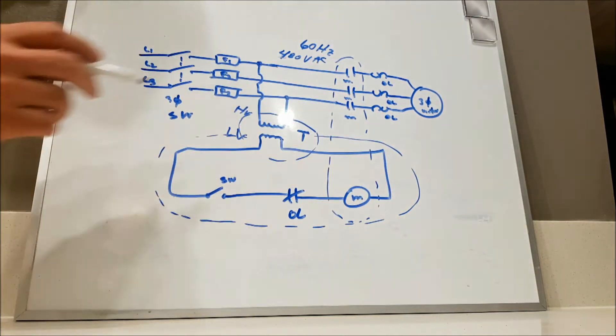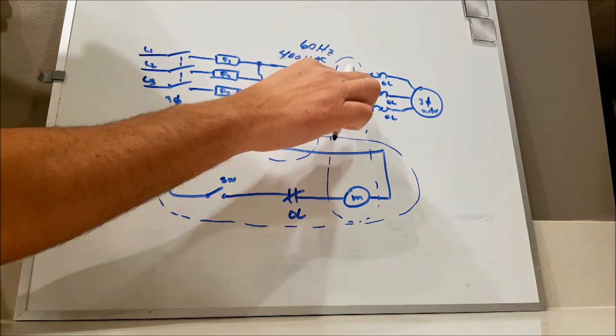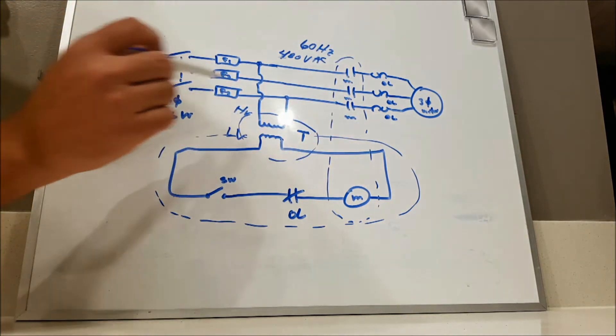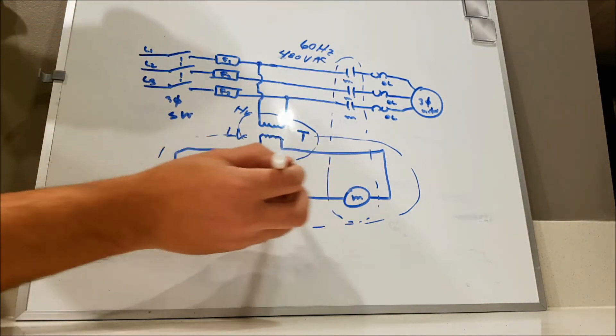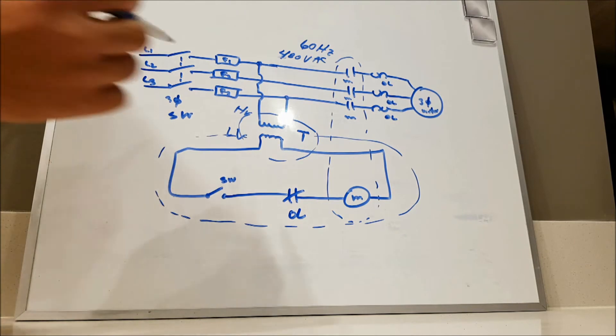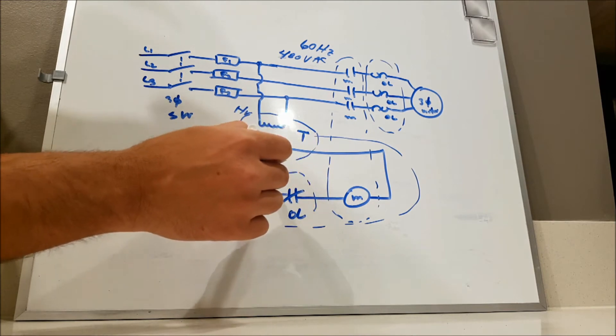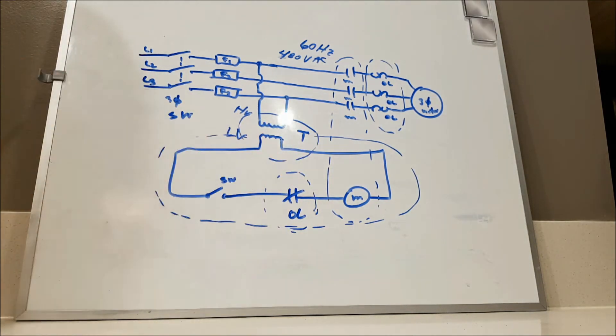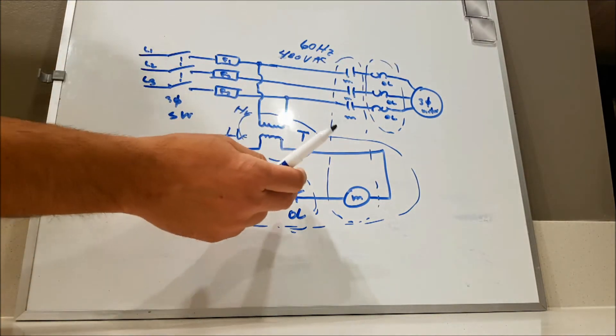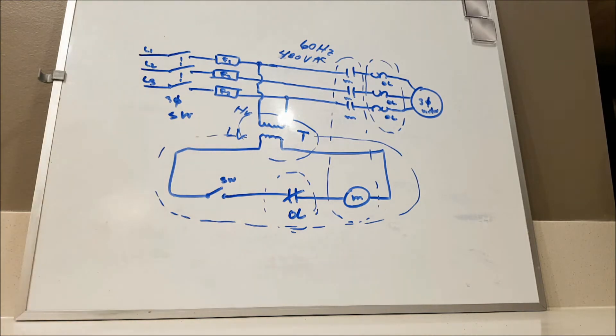Let's understand what a contactor is. We use a three-phase contactor which has three normally-open contacts and a coil. The coil is in the control circuit and the contacts are in the power lines. We also have an overload in each line for overload protection. There is an overload normally-closed contact in the control circuit — if an overload event occurs, this contact opens to stop current from flowing through the coil.